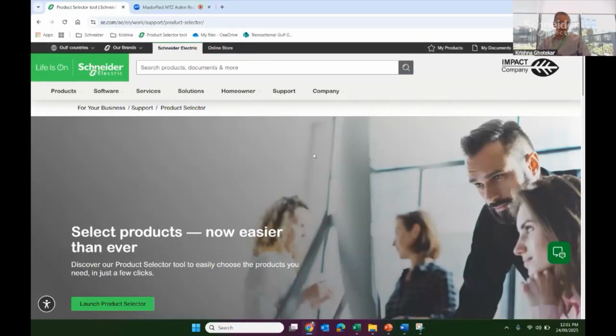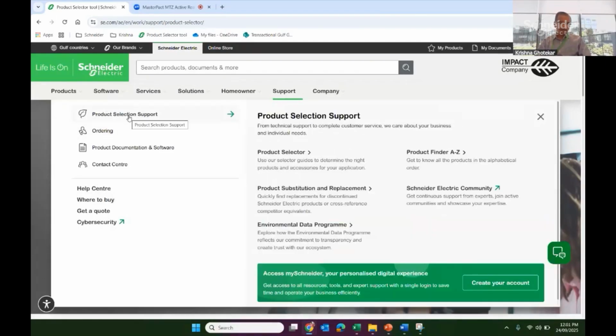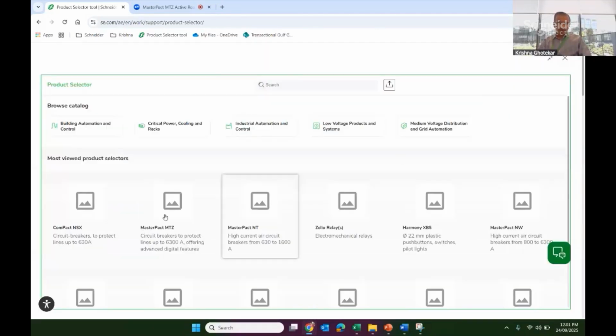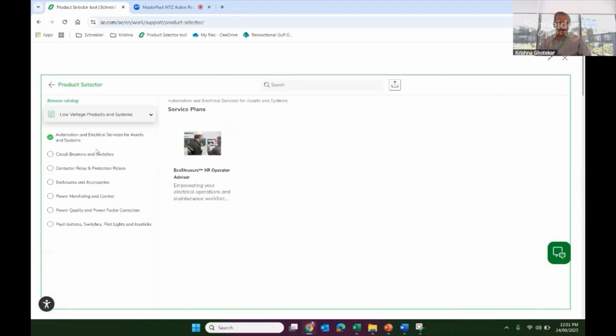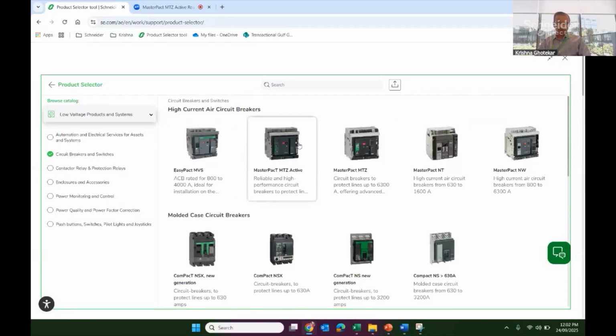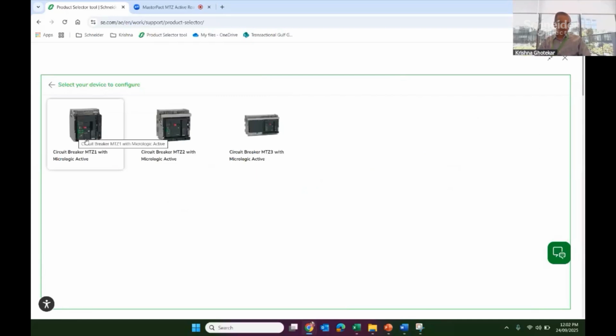the product selector. So I guess you are familiar. If you are not familiar, just go on Google and type product selector, or go to our Schneider Gulf website, se.com/AE. On that, you can go to support, and in support you have a product selection tab. Inside that, you have a product selector. So you just click onto that. It will open this, say launch product selector. You have some ranges. We can go to low voltage products, circuit breaker, and here you have EasyPact MVS, MTZ Active, MTZ, NT/NW. So if you go to MTZ Active, which one do you want, size 1, size 2, size 3? Let's assume I want a size 2 breaker.